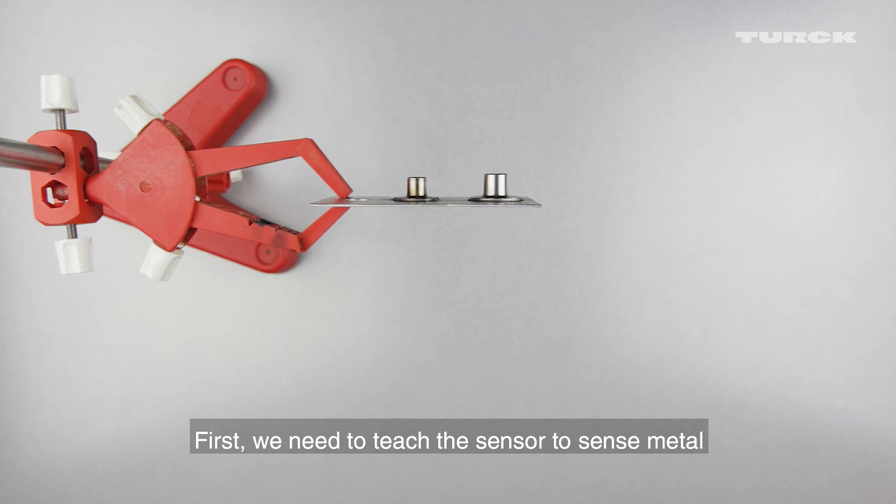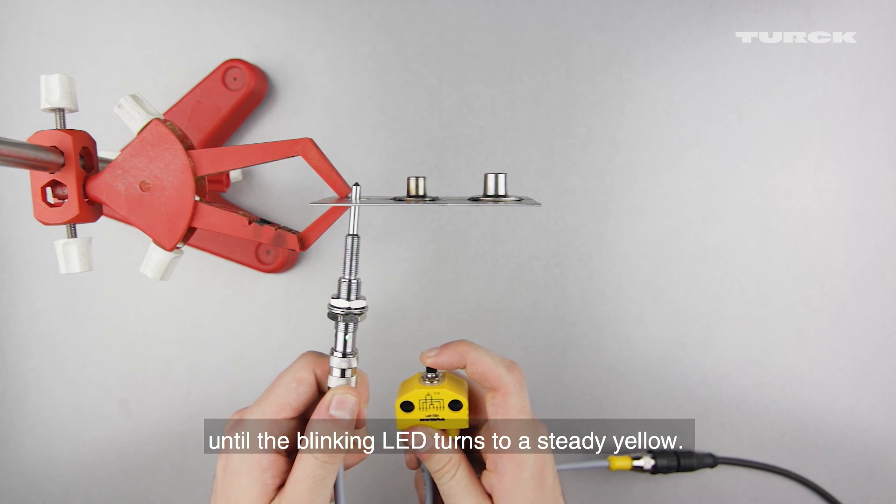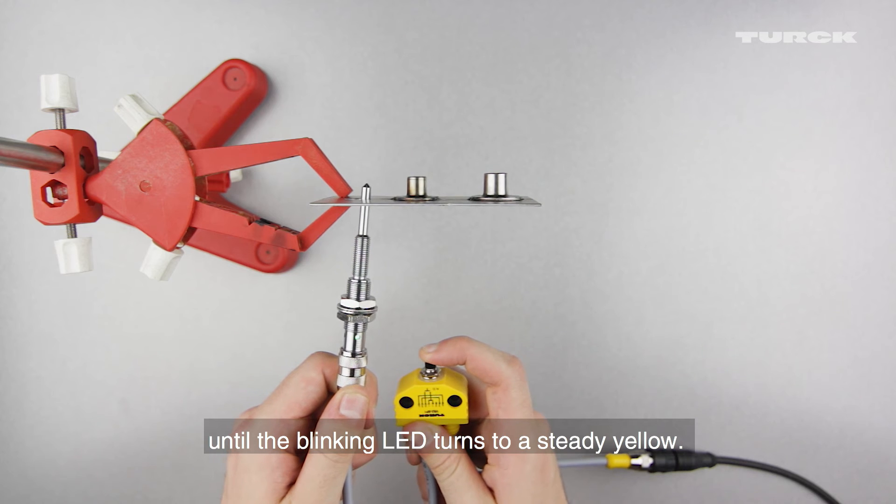First we need to teach the sensor to sense metal without the nut in place. To do this, insert the sensor through the mounting hole. Press the button of the teach adapter until the blinking LED turns to a steady yellow.